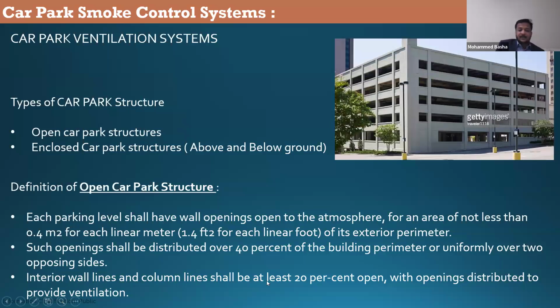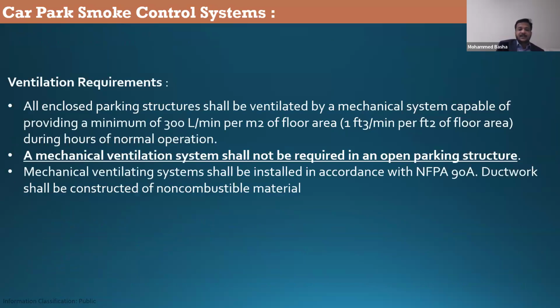Interior wall lines and column lines shall be at least 20% open with openings distributed to provide ventilation. This is the definition. If you have this, then it's called an open car park. If you do not meet any of these requirements, then it is not called an open car park structure. It is classified as an enclosed car park structure, which will warrant mechanical smoke ventilation and sprinkler systems. Of course, now sprinkler systems are required for open car park structures also. Previously, it was not required. What are the ventilation requirements? Open car park, we do not need anything because it's open.